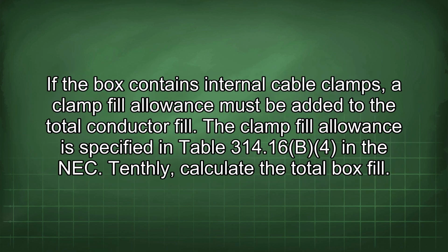Ninthly, determine the clamp fill allowance. If the box contains internal cable clamps, a clamp fill allowance must be added to the total conductor fill. The clamp fill allowance is specified in Table 314.16(B)(4) in the NEC.